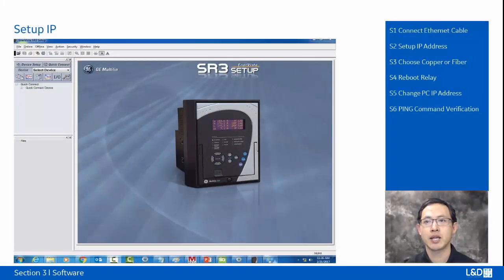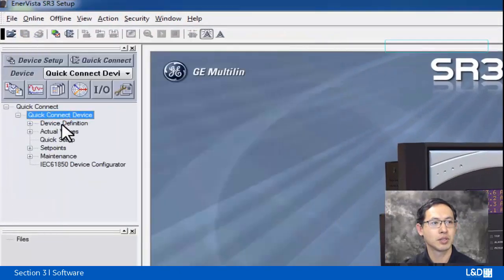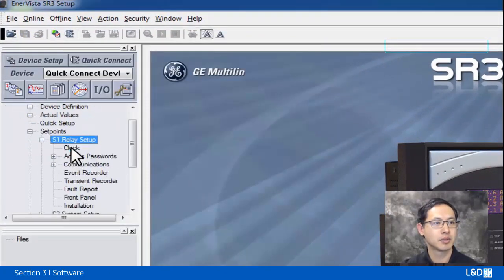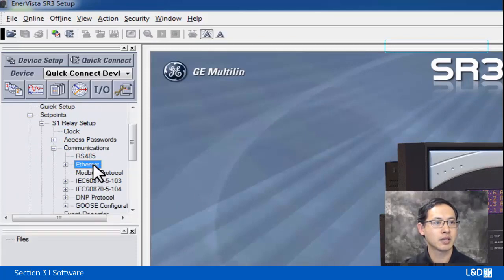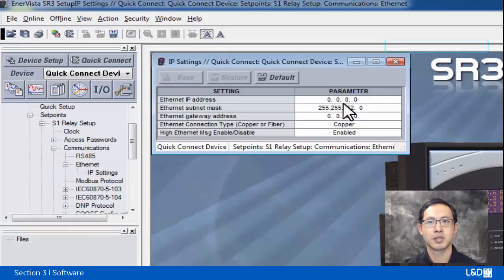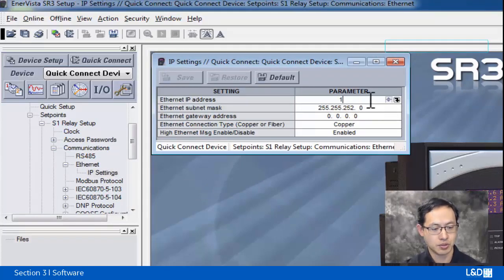The quick connection can be established not only through the front panel USB port but also through the Ethernet port. To use the Ethernet port, we need to set up the IP address of the relay. There are 5 steps to do this IP address setup. Step 1 is to connect the Ethernet cable to the RJ45 port on the back of the relay. And step 2 is to go to the relay setup, communication, and set up the IP address. So in this case, we're going to use 1.1.1.1 as an example.